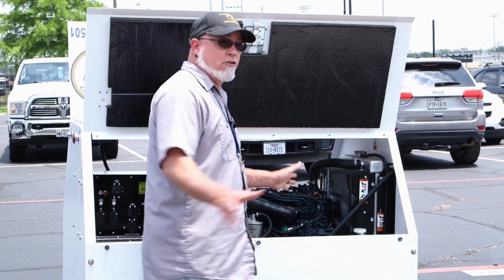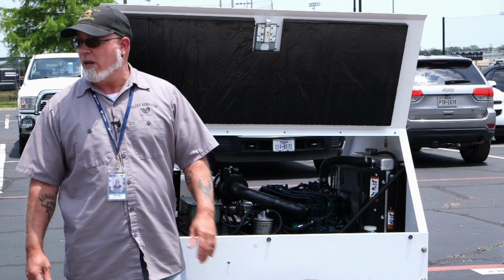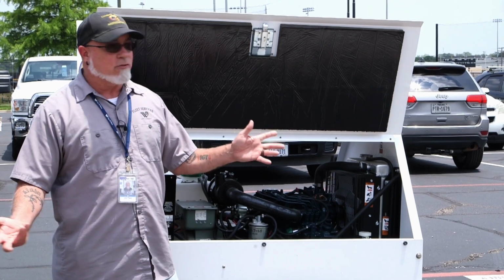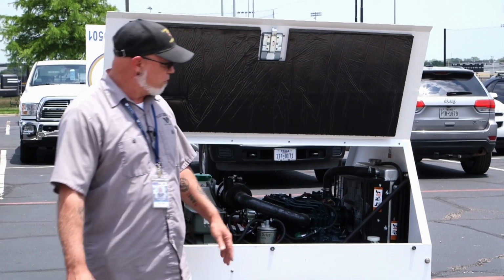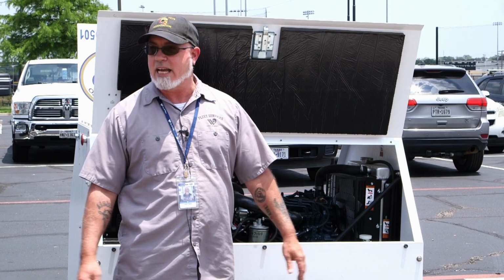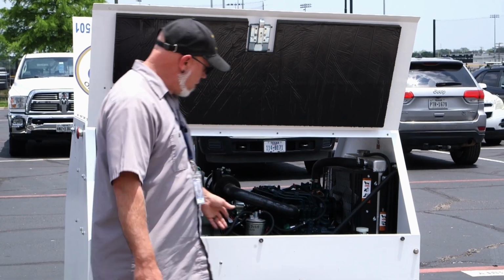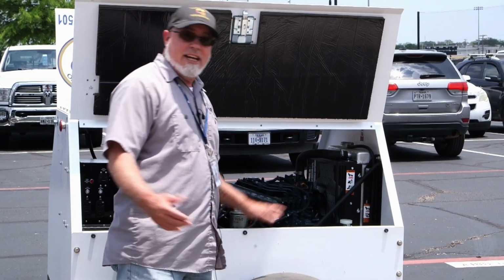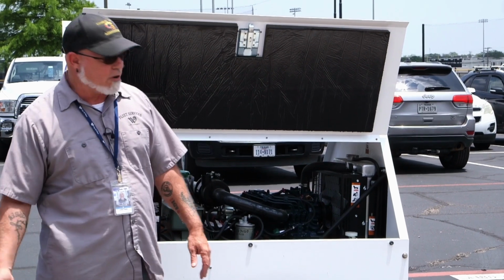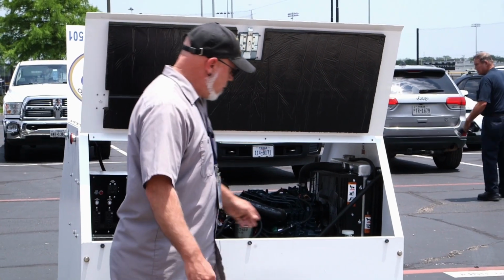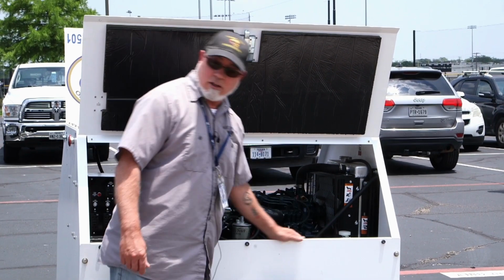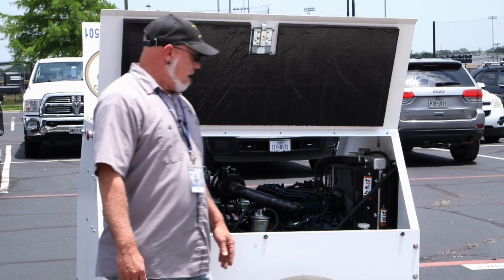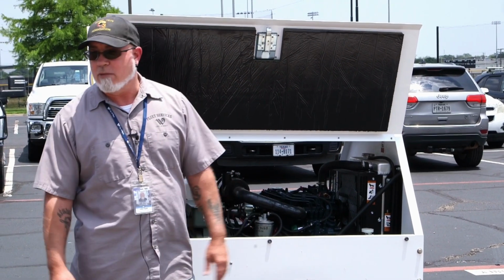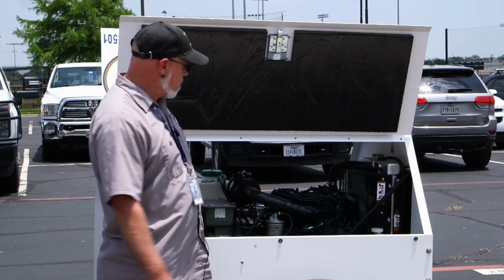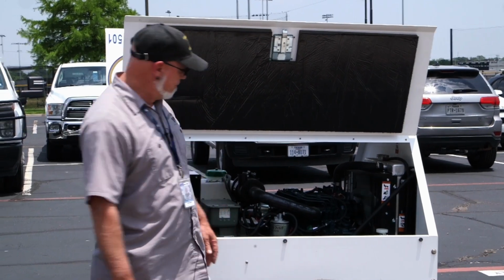Before you start any piece of equipment, or if it's on some type of scheduled or remote startup, you should have a scheduled plan to check the oil. You always want to make sure your oil is in good shape and at the proper level before starting any engine. Check the coolant level as well, make sure it's topped up. All that should be on some type of daily, weekly, monthly, or quarterly scheduled maintenance program.